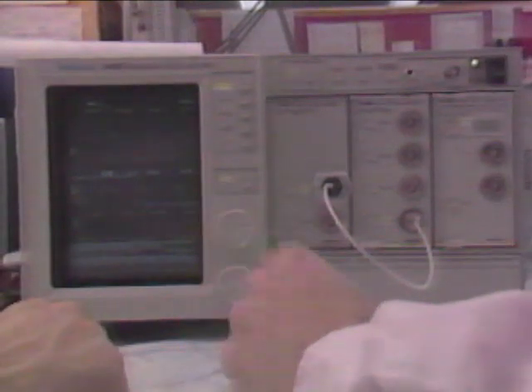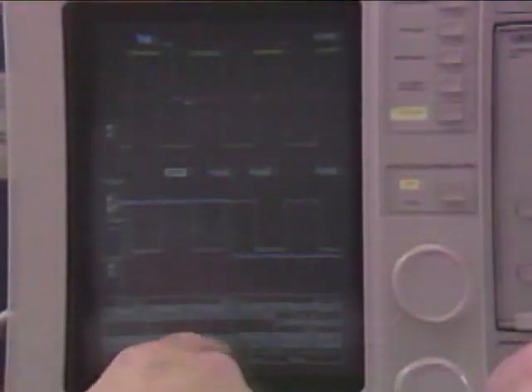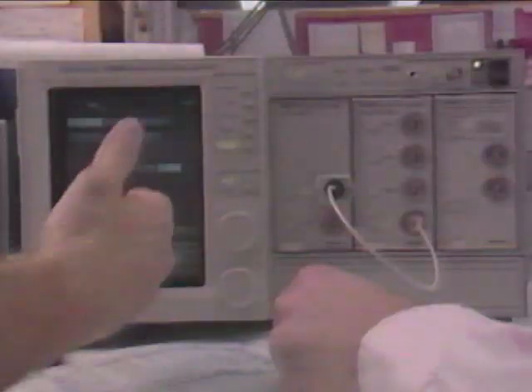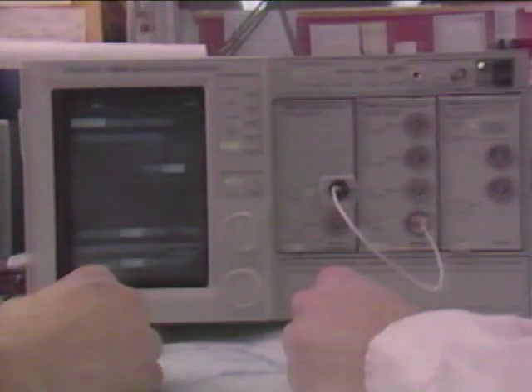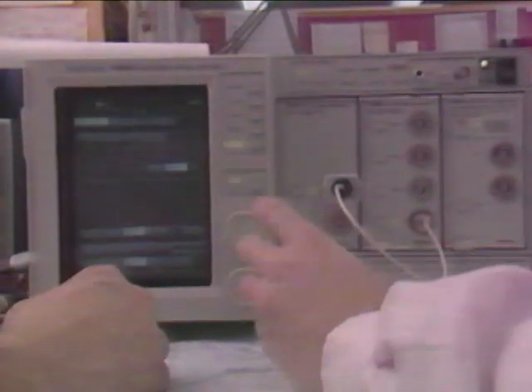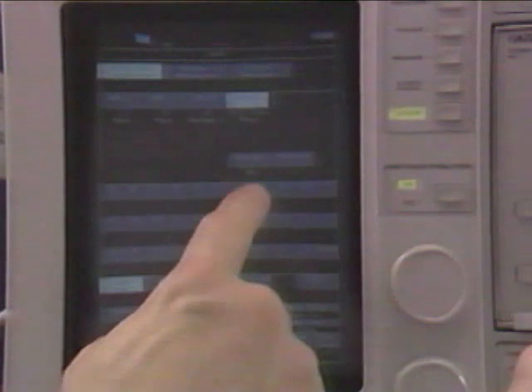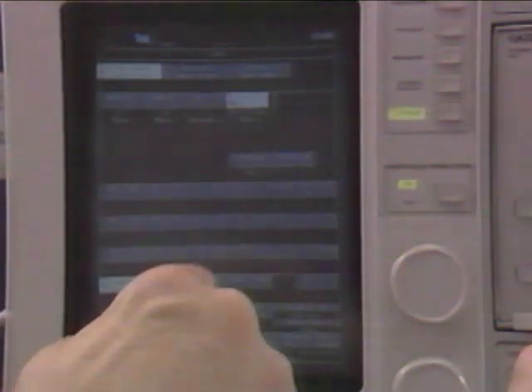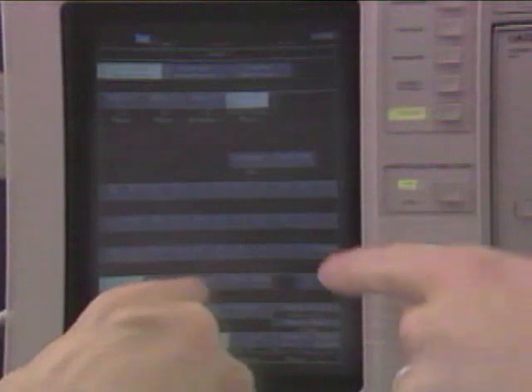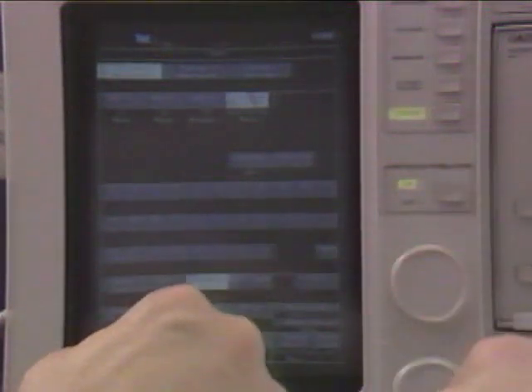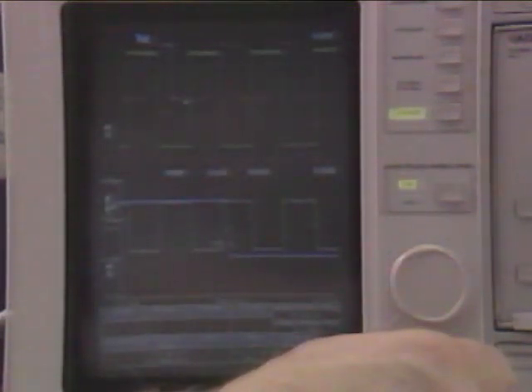Okay, well, try this. Here, select utility menu. Oh, me? Yeah. Okay. Now, go ahead and touch the label block. What's this? My own typewriter right on screen? I can write my mother from here. Actually, it's a lot more functional for labeling. So, go ahead and select a waveform. Say five. And now change it over to uppercase. And enter a pin number. P-I-N space. And then go to numbers. Up here, there. About four. Okay, now hit position. And use the knob here to position it where you want. Ha! Fantastic! This is worth its weight in grease pencils.